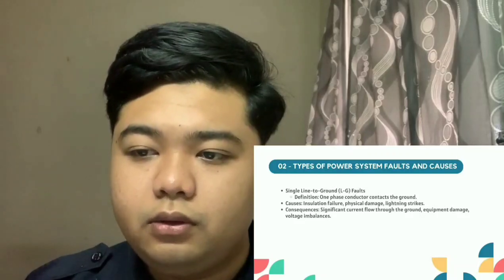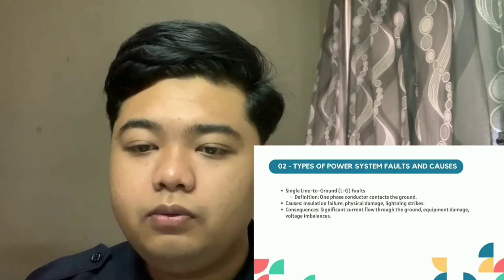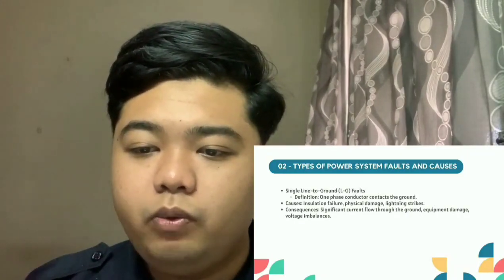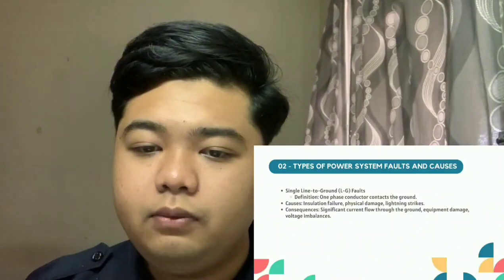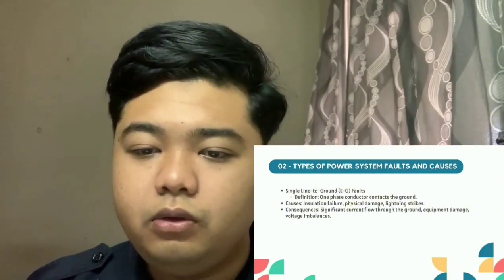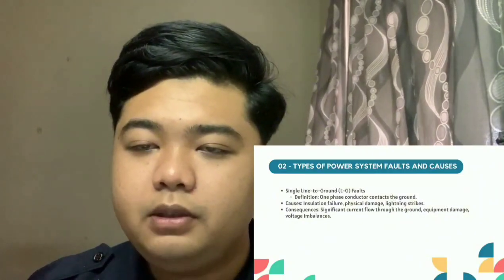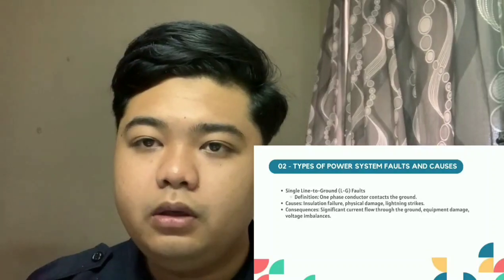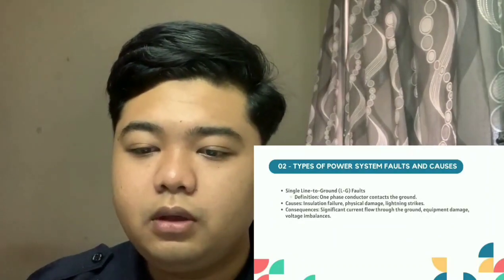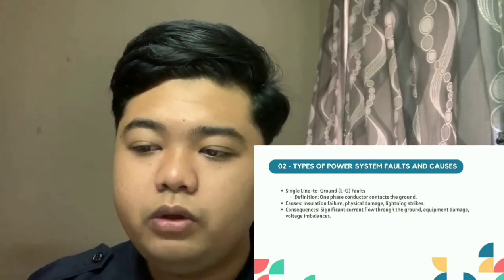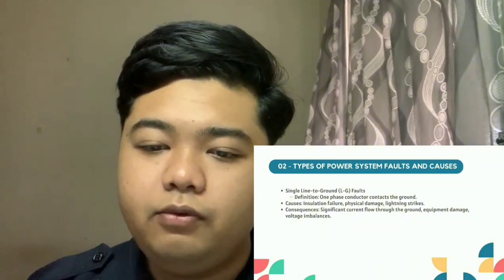The next fault is the single line to ground fault, which is when one phase conductor contacts the ground. The causes are insulation failure, physical damage and lightning strike. The consequences of this fault are significant current flow through the ground, equipment damage and voltage imbalance.